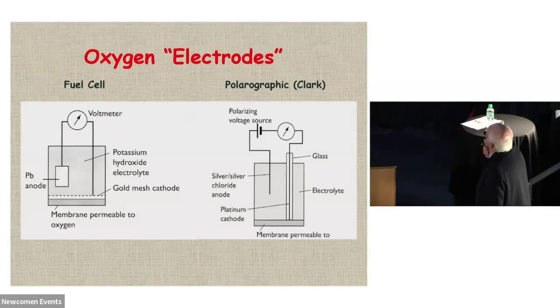But this lasts a lot longer. It's the same membrane that's used, and the voltage here is 0.6 of a volt, and the platinum electrode here with glass insulation. And anyway, the concentration of oxygen this side of the membrane gives you a linear indication of the current passed through. It will last much longer than a year, as long as you don't poison the membrane.